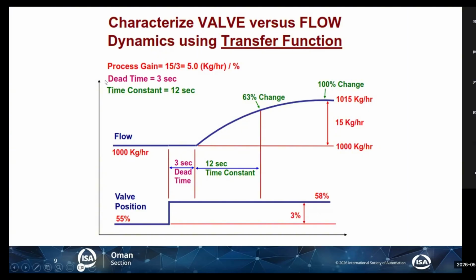And then I have something called dead time, which is something like you can say nature in the controller. When I change the valve position from 55 to 58, you can see here there are 3 seconds with no change in the CV. This is our dead time, and it is also very important to understand. And then there is something called our time constant. Later on I will explain mathematically that we represent time constant as tau and dead time as theta, and these are used in tuning also.